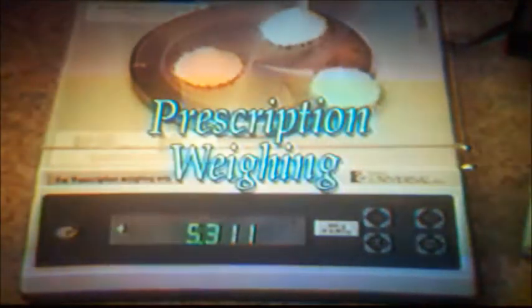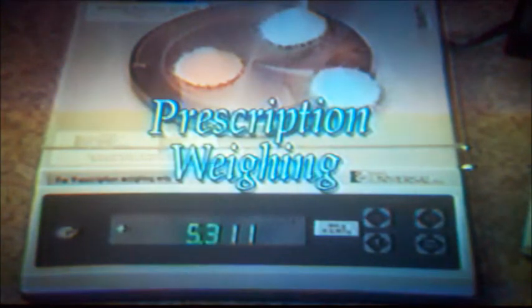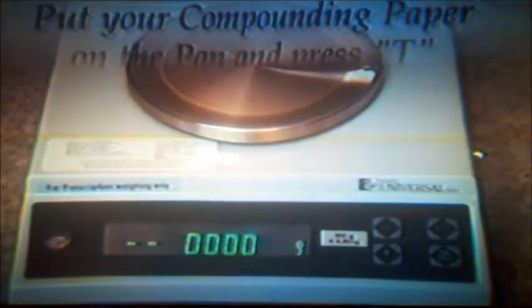Your new Baker Universal also serves as a prescription scale. As you'll remember, when you were calibrating the unit, you were shown how to toggle between counting and weighing by pressing and holding the T button. When the display indicates no G, release the T button. Put your compounding paper on the pan and press T. This will zero the value of the paper.